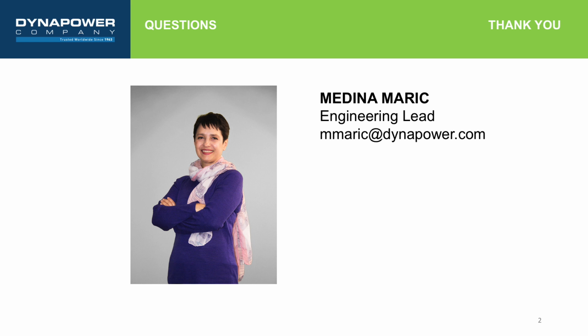The harmonic difference is really dependent on the transformer configuration to any rectifier or drive for that matter. 6 pulse, 12 pulse, 24 pulse: the harmonics generated by these configurations are the harmonic numbers on either side of the pulse number, at 1 over that number. So a 6 pulse rectifier has 5th and 7th harmonics, 1 over 5 or 20% 5th, and 1 over 7 of the 7th harmonic.